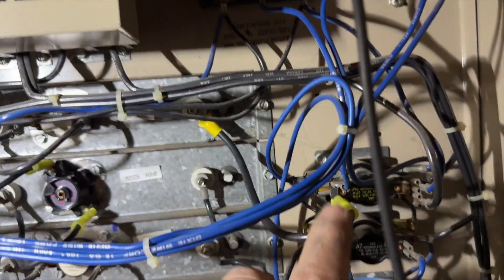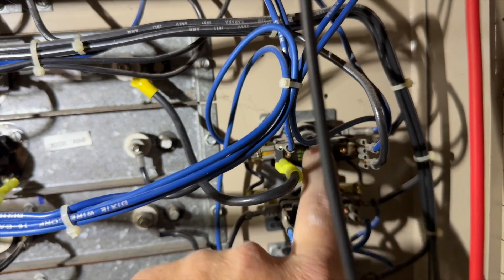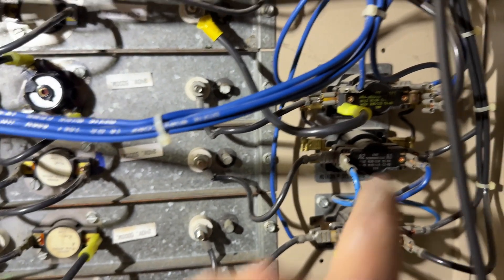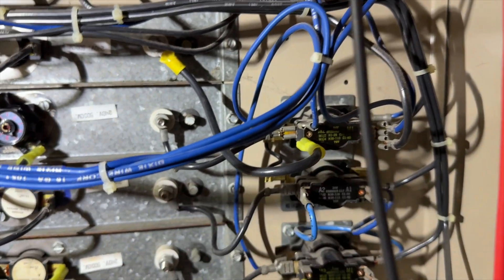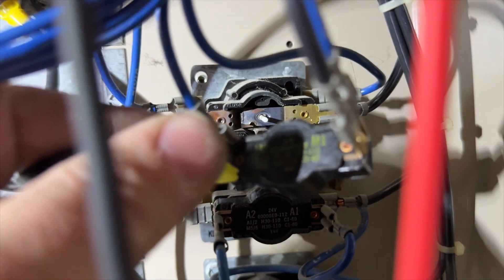So after checking, only these two circuits were running, and I just found out there's no call for heat. So this is stuck closed. We need to see what's going on with that. I'm gonna change these out, and then we'll try cycling things. Closer inspection, this thing's melted.